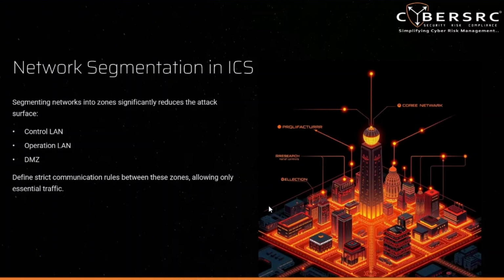DMZ: use the DMZ for securely aggregating ICS data and providing controlled access to the enterprise network. Incorporate application layer gateways to sanitize data and deploy one-way data diodes. So now it will ensure that there are no malicious commands entering my device, but all the necessary information is flowing out of my device, where the unidirectional flow is required for high security.